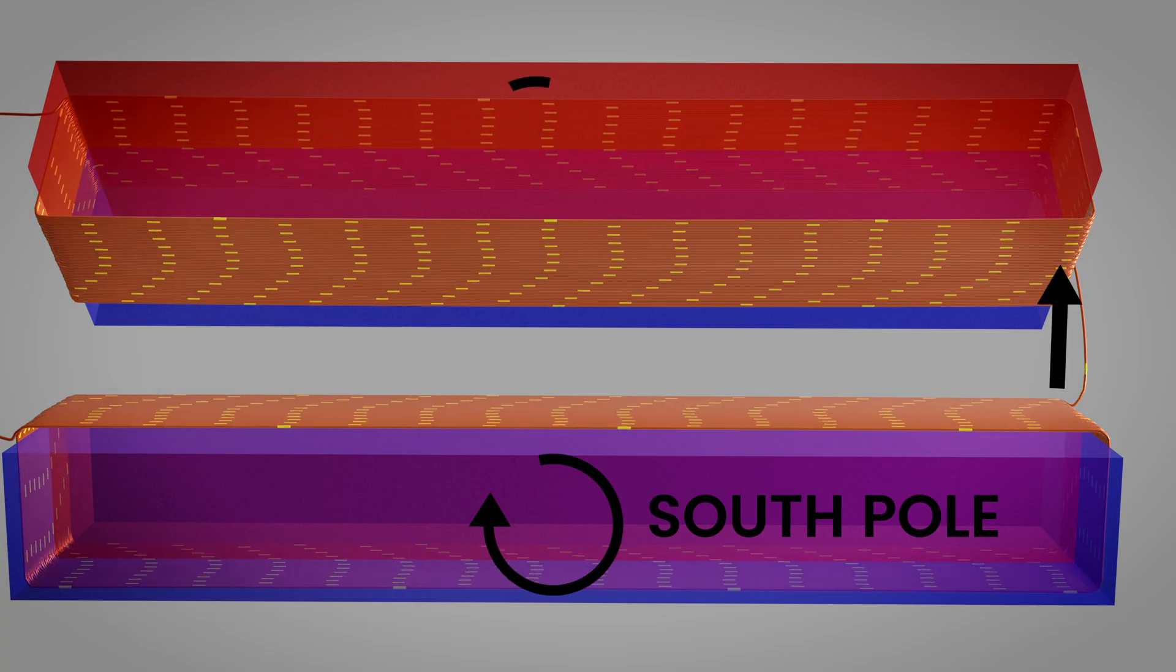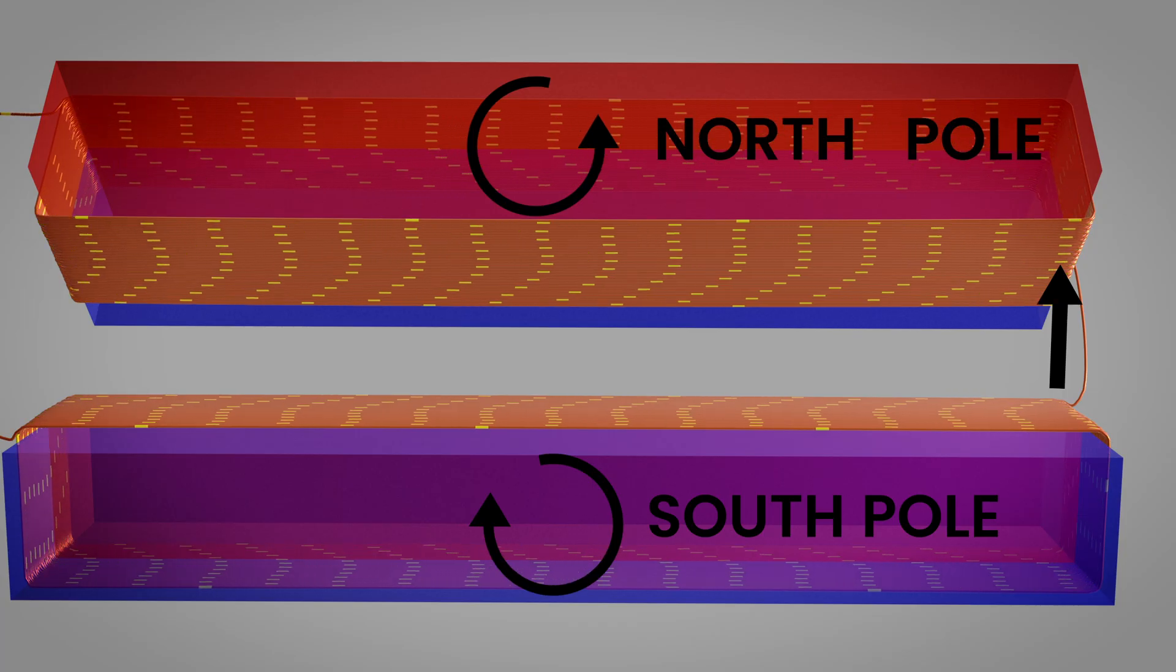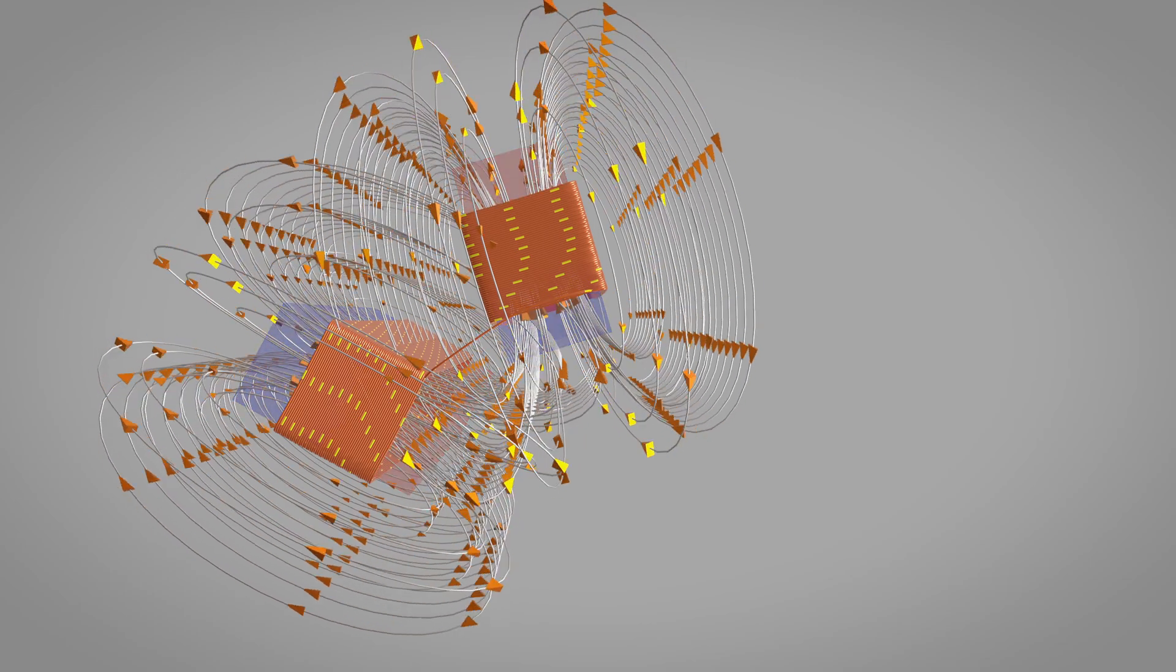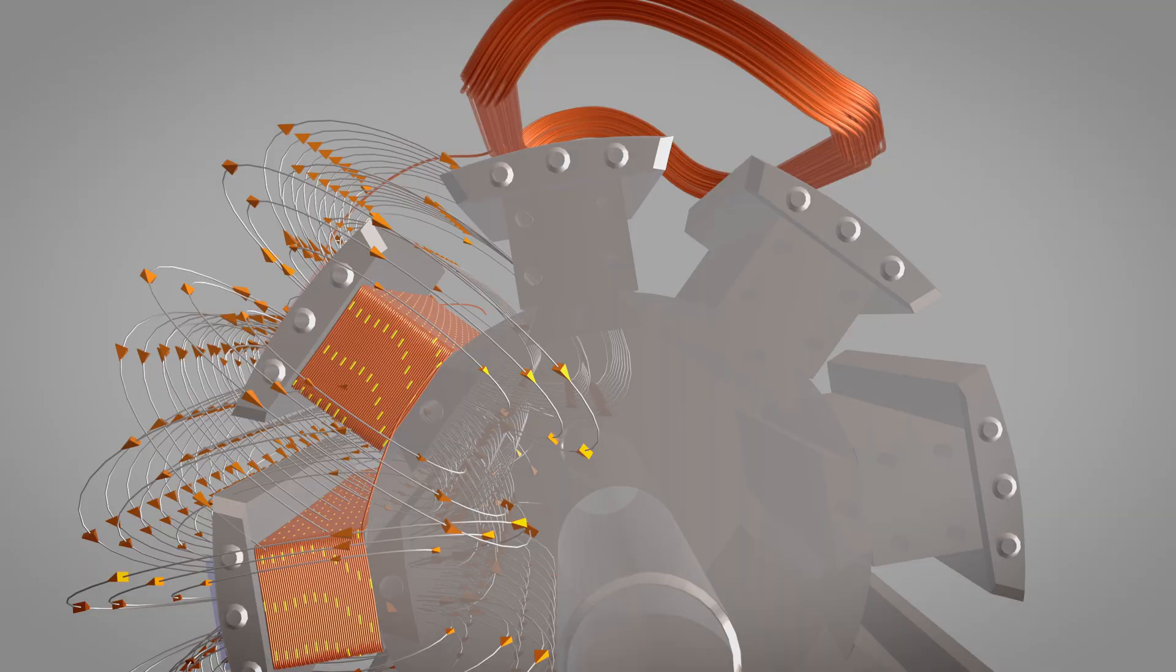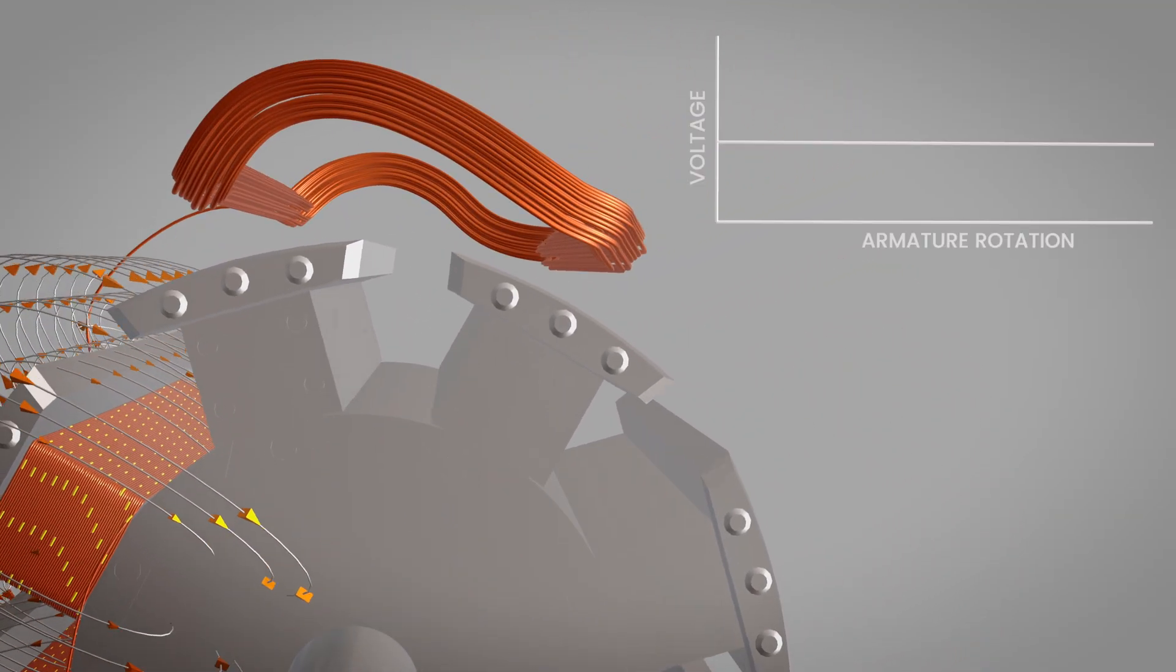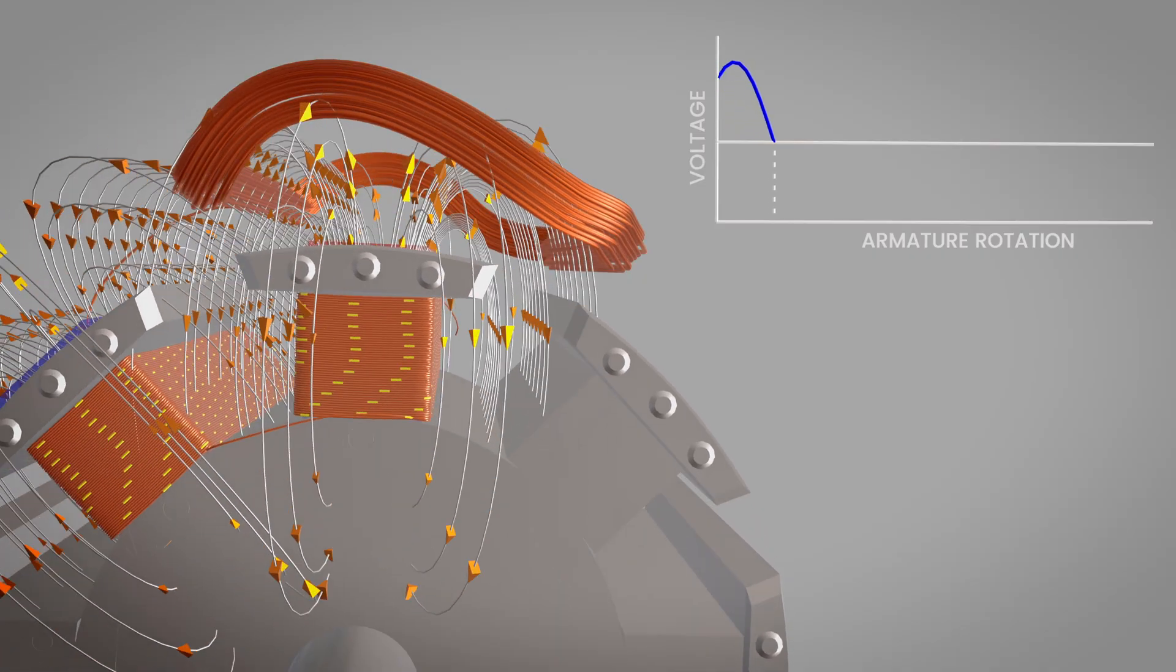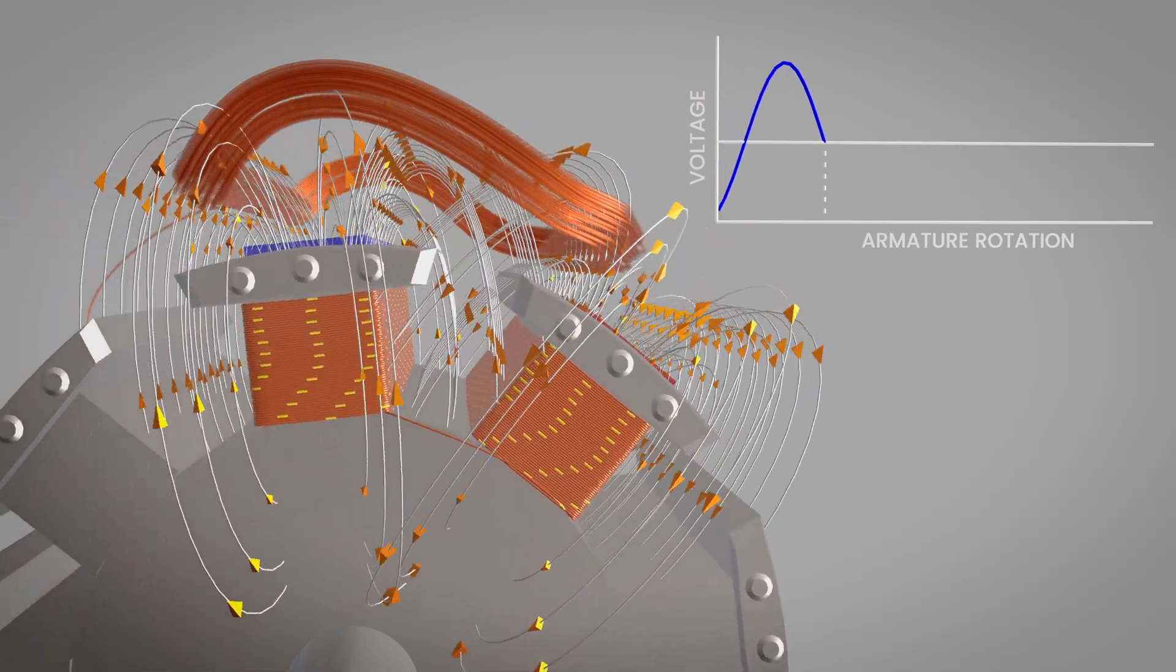The current then continues to the second pole, where it flows counterclockwise, creating a north pole. This series connection of field windings is essential. It ensures that adjacent poles always have opposite polarity. As our two-pole rotor spins, the single stator coil experiences alternating magnetic fields. As the north pole passes our stator coil, induced voltage rises to its positive peak. As the rotor continues and the south pole approaches, voltage decreases, crosses zero, and reaches a negative peak.